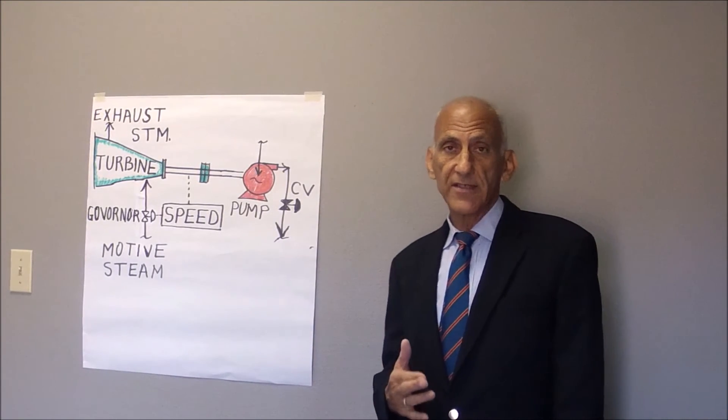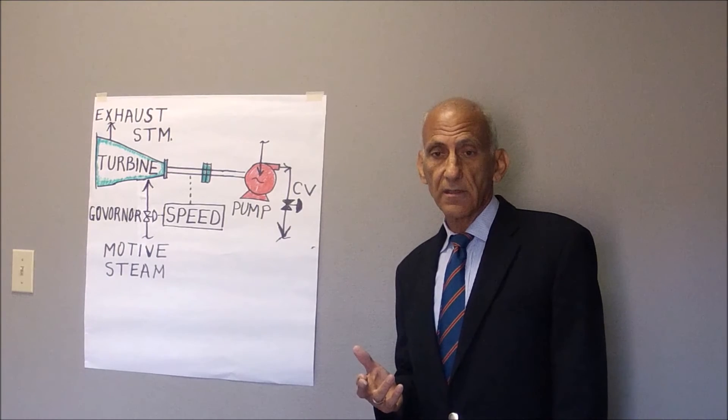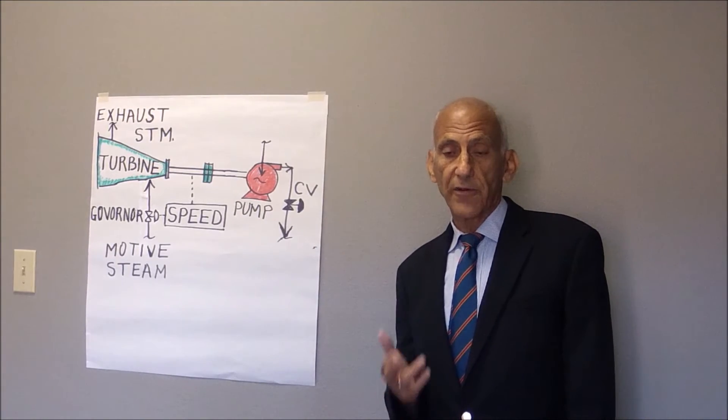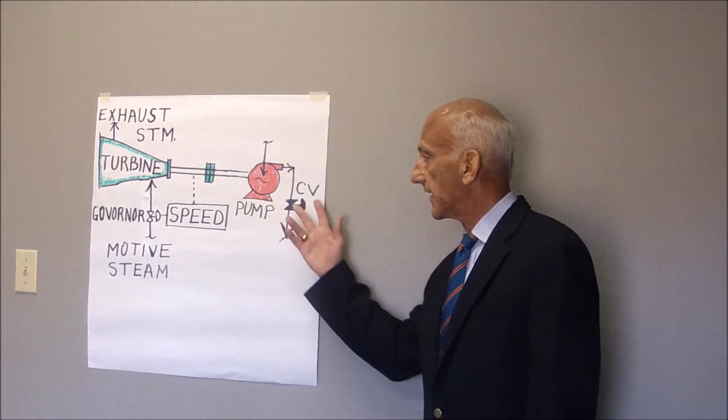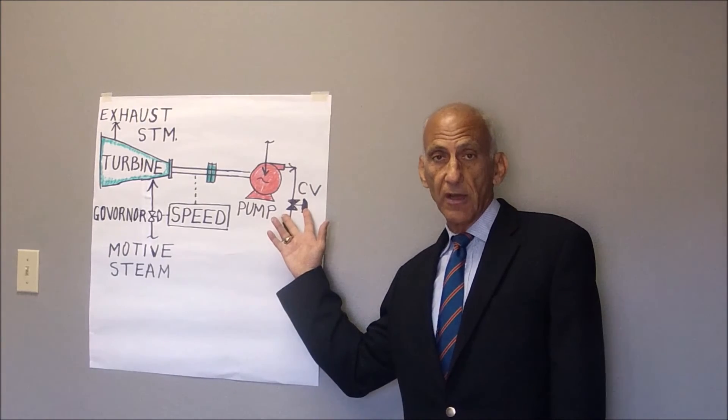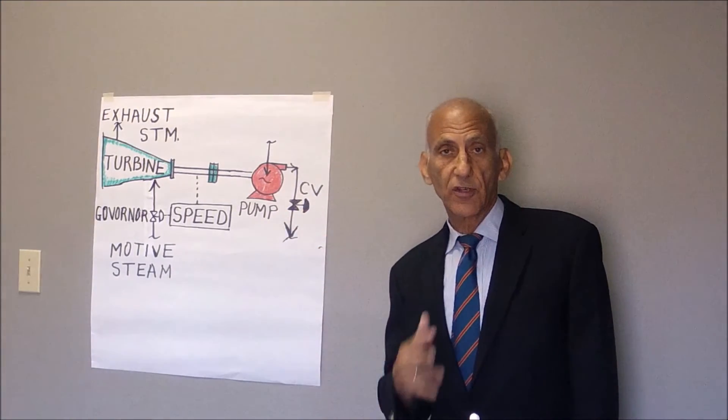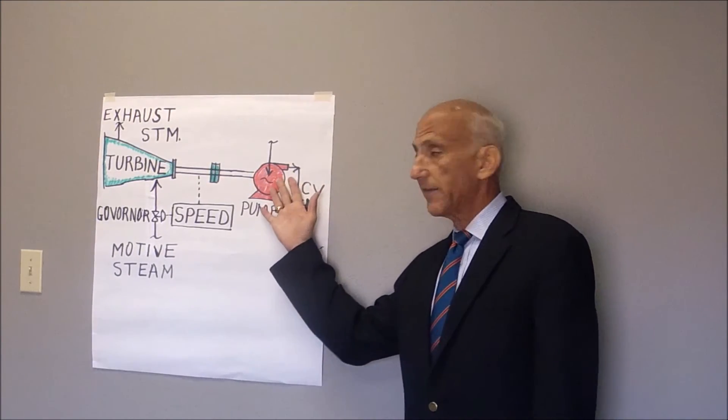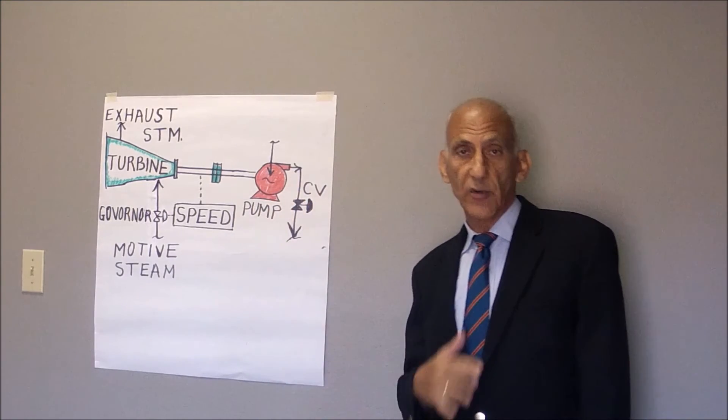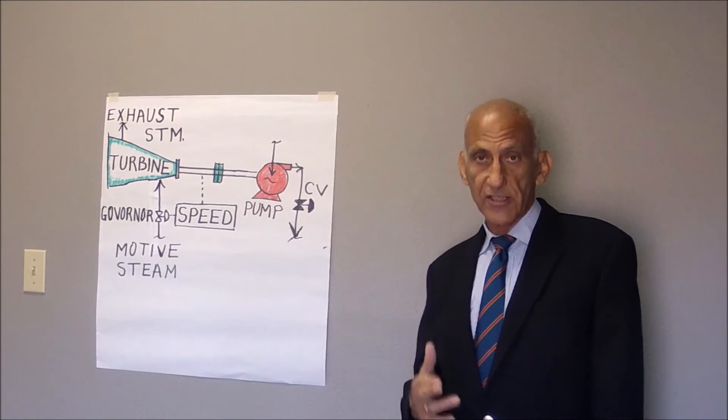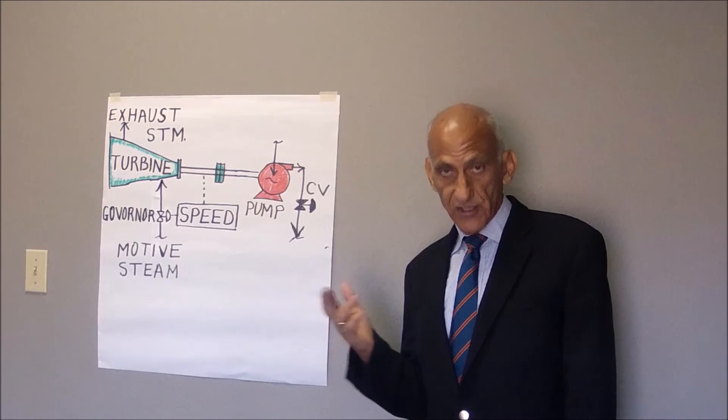Now, this raises two other questions. The first question is, perhaps you don't actually need this valve on the discharge of the pump. Perhaps you can control the flow delivered by the pump simply by directly adjusting the turbine speed. And that's done all the time.